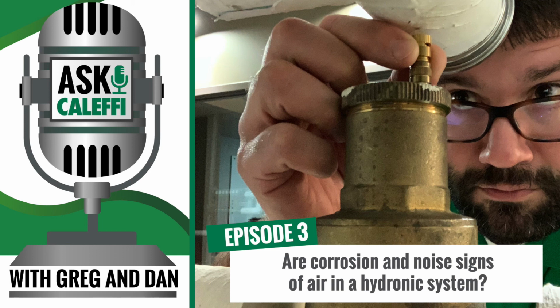Right. We've covered some service. We've covered sizing and installation, how these things work. How big of a unit do we make? All the way up to a 12-inch unit. It's pretty impressive. You look at our 12-inch unit, that thing is rated for 3,530 GPM. That's a lot. That's a big flow rate. That's huge. Think of 3,530 gallons per minute of flow.